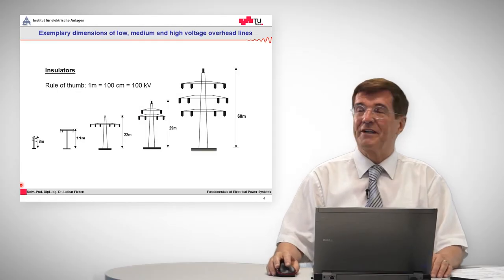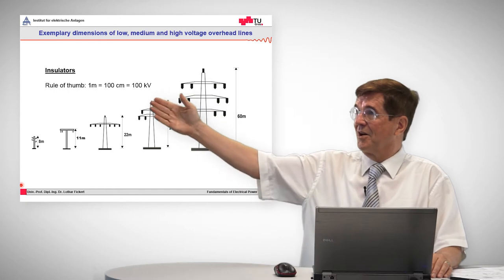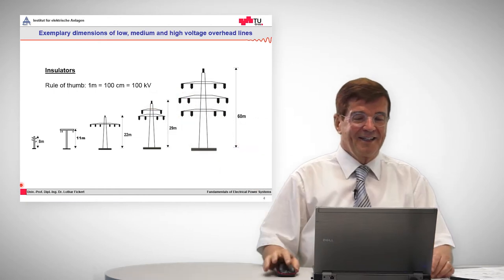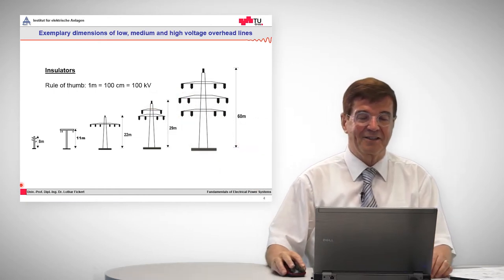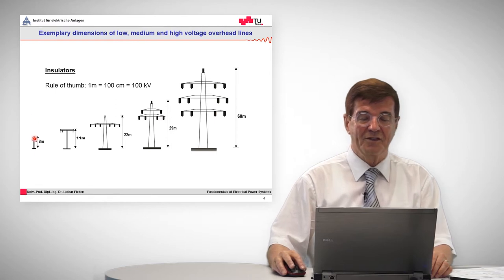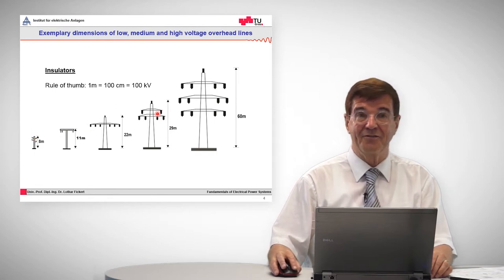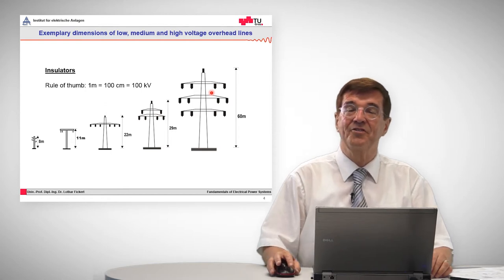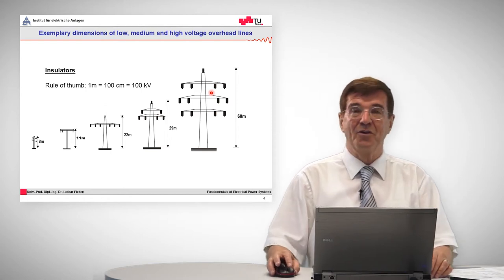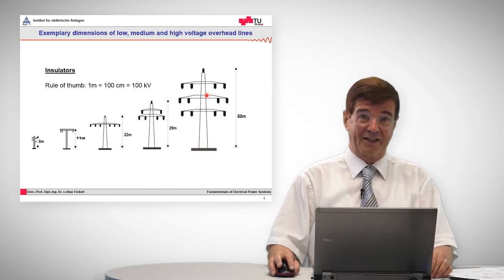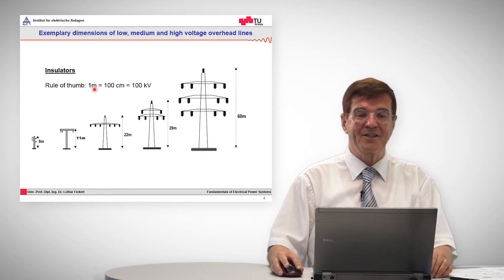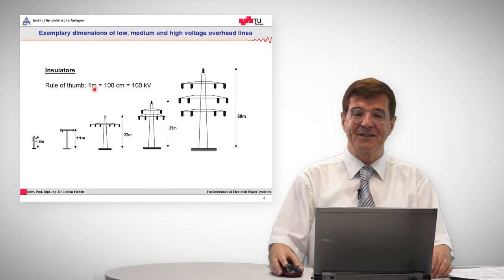We all know the overhead lines which we can see. They are constructed for small voltages to medium voltages, high voltages, and extra high voltages. There's a common rule by which you can determine what is the transport voltage of a given overhead line. The rule of thumb is that one meter, or 100 centimeters, is 100 kV of system voltage.